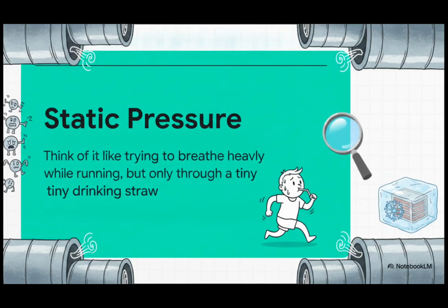Now, pushing all that air through those narrow metal floor trunks creates what HVAC pros call static pressure. It's basically the high air resistance measured inside those ducts, which typically runs at about 0.70 to 0.90 inches of water column in mobile homes. Think of it like trying to breathe really heavily after running, but doing it through a tiny drinking straw. Tough, right? Well, if the airflow gets too weak against that resistance, it can literally freeze your indoor cooling coil into a solid block of ice right in the middle of summer.